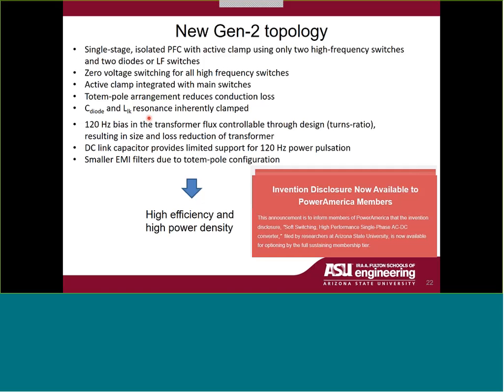Operation-wise, it is more or less similar to what I described, just that we don't have a separate main switch and active clamp switch. The functions are done by a combination of the 2 high-frequency switches. So during the positive half cycle, one acts as the main switch and the other as the active clamp, and vice versa for the negative half cycle of the sine wave.